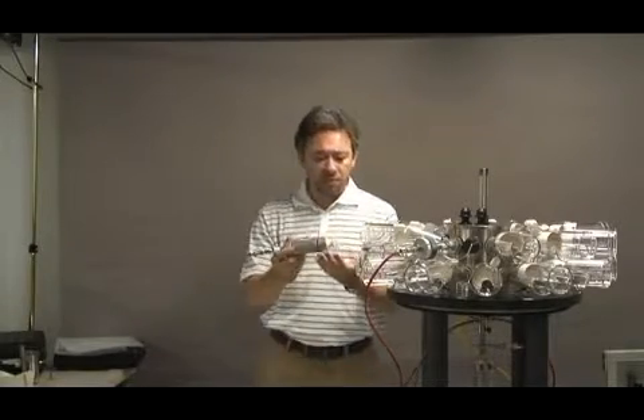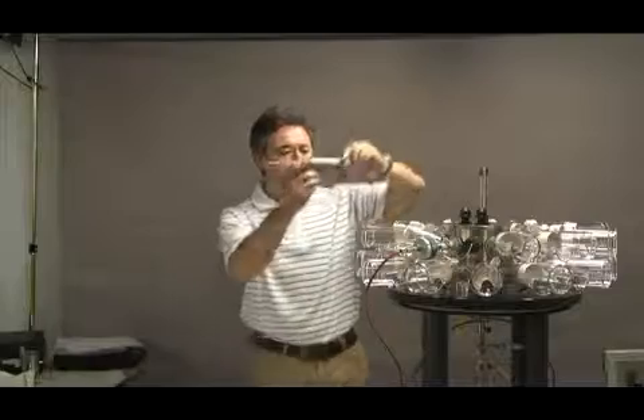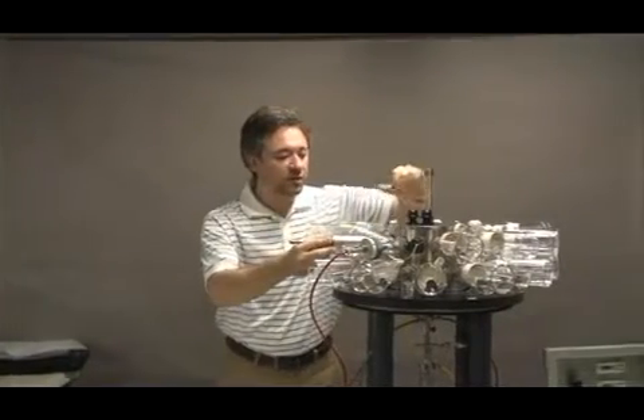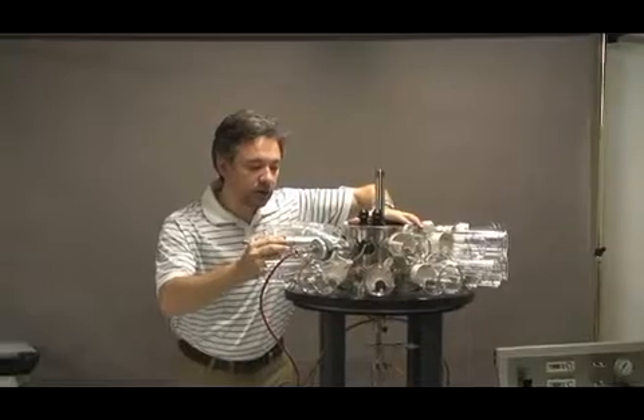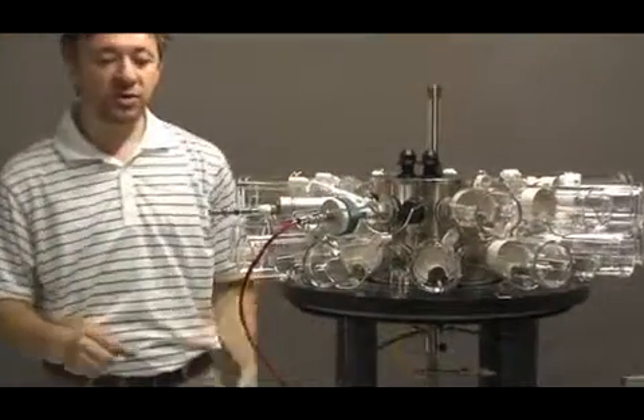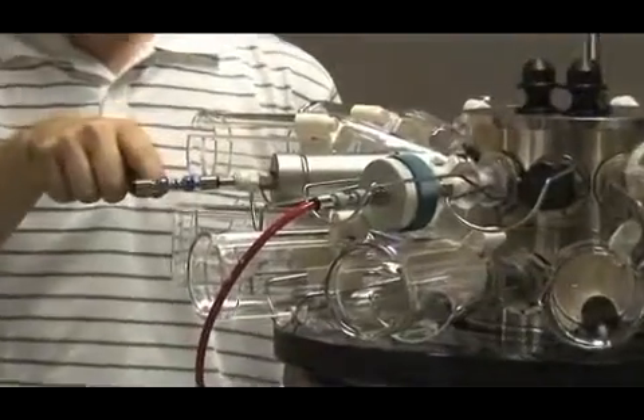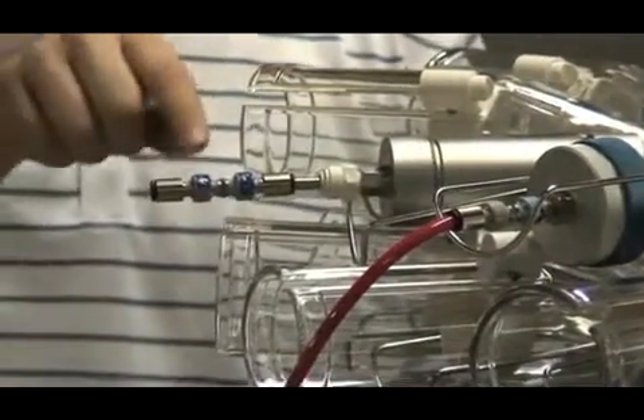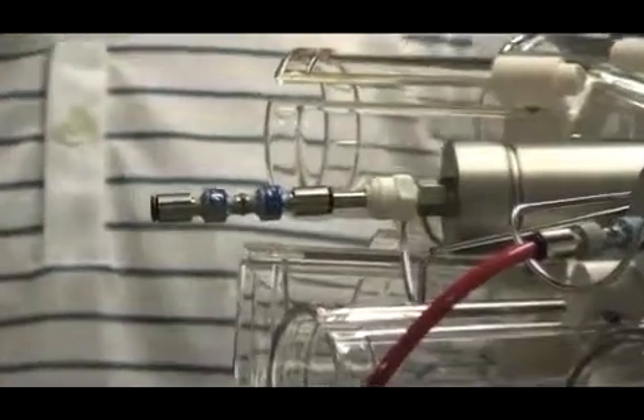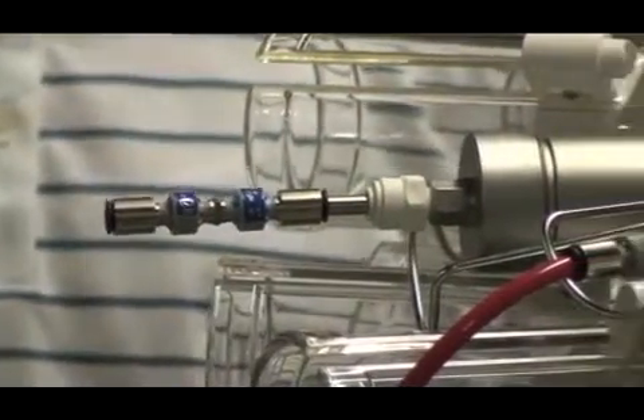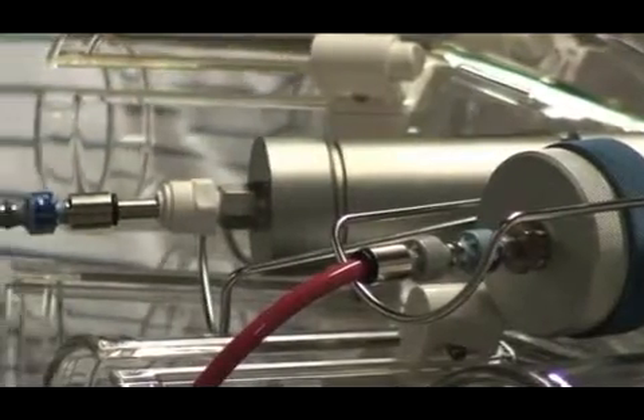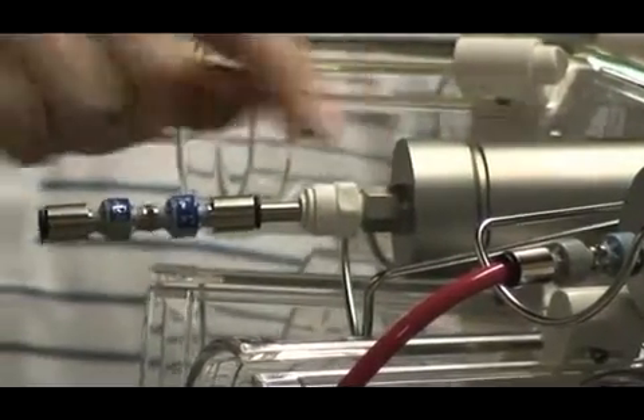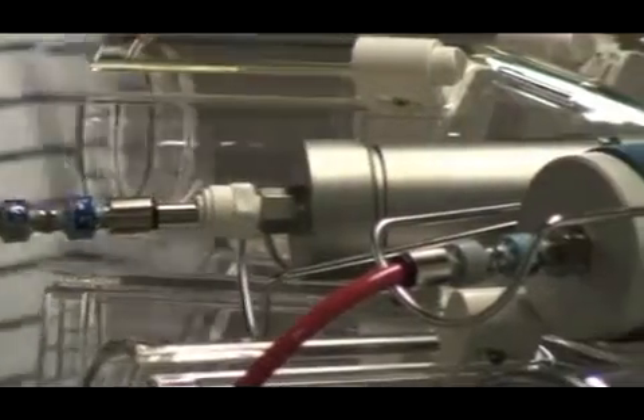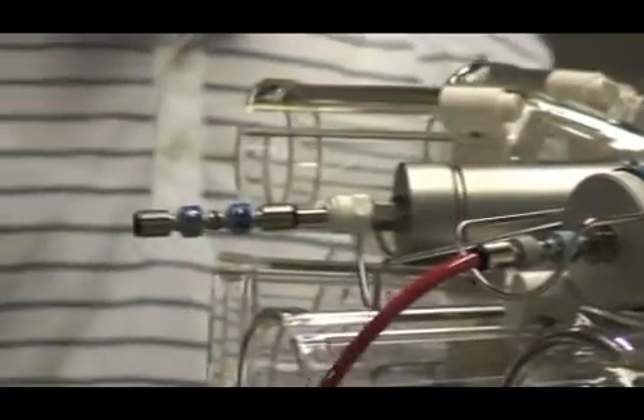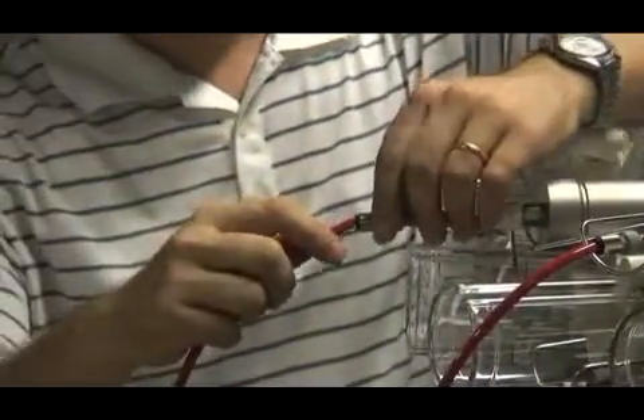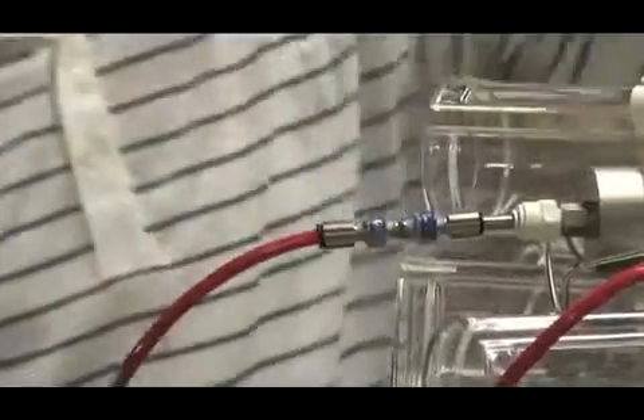The way you operate the impactor is exactly the same as the filter. Attach the impactor into one of the sampling ports. The impactor also has a calibrated choke, so every time you measure with the impactor you have to calibrate the flow rate of the choke, and it has a pre-filter to protect the choke from any particles that escape the impactor. So the same way as with the real-time monitor, you just attach one of the sampling lines.